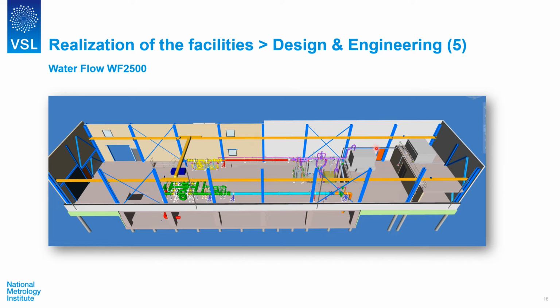The largest one you can see here, that's a 10-ton weighing scale. Next to the larger customer test section, we have a smaller one that you cannot see very clearly in this picture, but it's here. That's for the smaller meters, where we also have a Coriolis master meter section as master meters for calibrating flow meters. In this picture, you also see a 3.5-ton weighing scale in the basement, where we can calibrate flow meters, but also do volumetric instruments, so test measures. We can put even a truck on the outside of this building and flow into this 3.5-ton weighing scale.